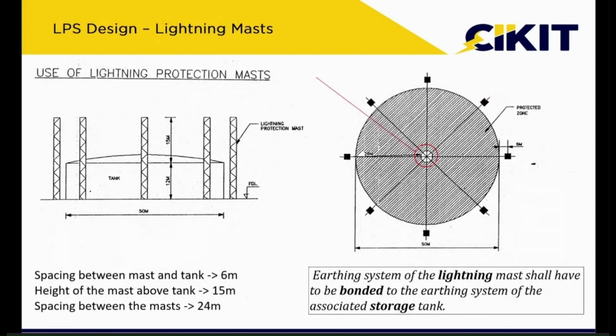The second method is by using a lightning mast. Here we won't be placing the air terminals on the structure itself. The reason is that if it is an existing plant and I want to install it, the welding of air terminals is not allowed inside those particular areas, since welding can result in fire accidents. So if you don't want to weld any other structures or make any alterations in the tank body, then we can go for providing the mast surrounding this perimeter.